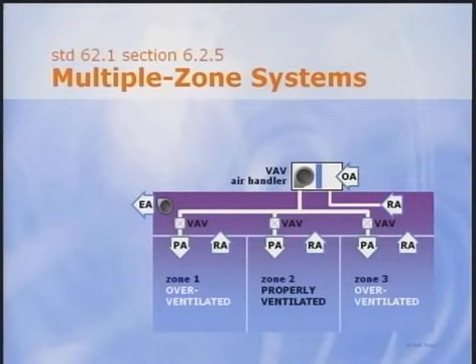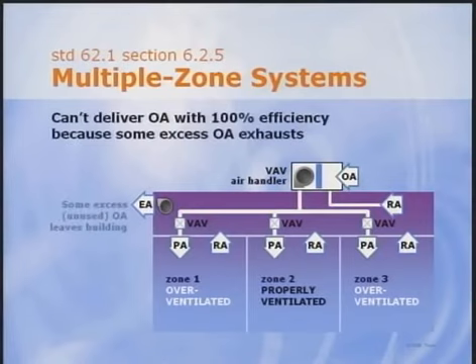Remember, in a multiple zone recirculating system, one air handler supplies a mixture of outdoor air and recirculated air to more than one ventilation zone. The outdoor air needed at the intake depends on the outdoor air required in all zones and how efficiently the system delivers it. One zone, the critical zone, determines the outdoor air fraction required in the primary air. All non-critical zones receive the same fraction of outdoor air, even though they don't need this much. So the critical zone is ventilated properly, but all other zones are overventilated. This means that some unused outdoor air recirculates, but some leaves the building. So system ventilation efficiency is less than 100%.